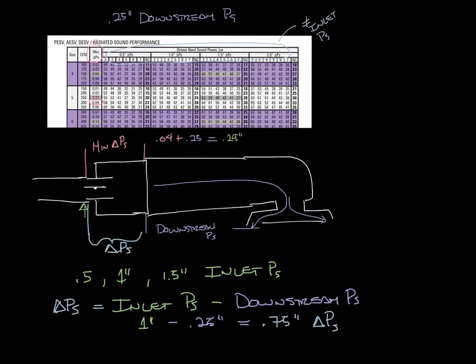If you remember, pressure-independent VAV boxes open and close their dampers to control the airflow regardless of changes in pressure in the system. As the damper closes, the pressure drop will increase across the box, and that makes the sound go up. It's important to know the difference between your inlet pressure and your delta P, because if you're comparing data from two different manufacturers, you don't want to compare 1 inch inlet pressure to 1 inch delta P.